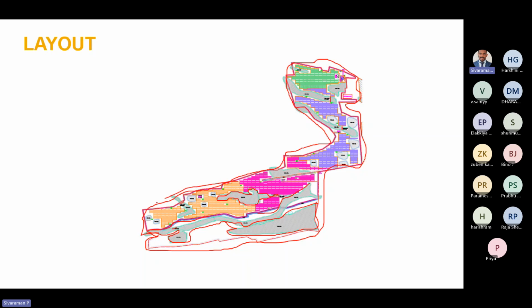So here in this area, some lines are there, right? Some shadow is there, right? These shadows are the solar PV modules, where we are going to install the solar PV modules. This is that area. The light brown color is the module installing area. So this will be inverter room 1. This is the inverter room, short form IR1. In the inverter room, we are going to have the inverter, then the inverter duty transformer, switch gears, including low voltage switch gear, high voltage switch gear, and auxiliary equipments. Those things will be there in this inverter room.